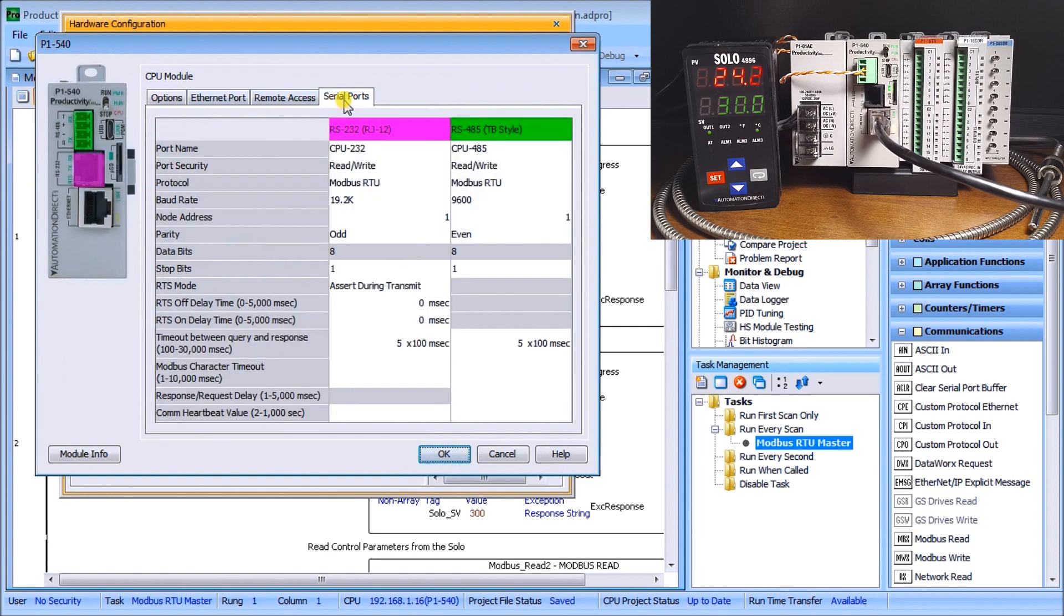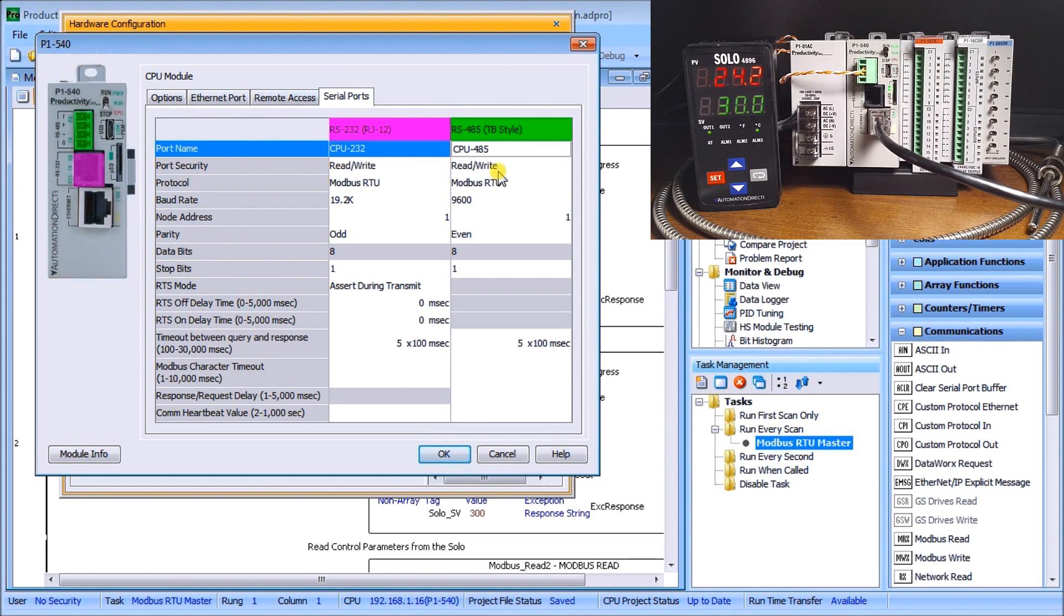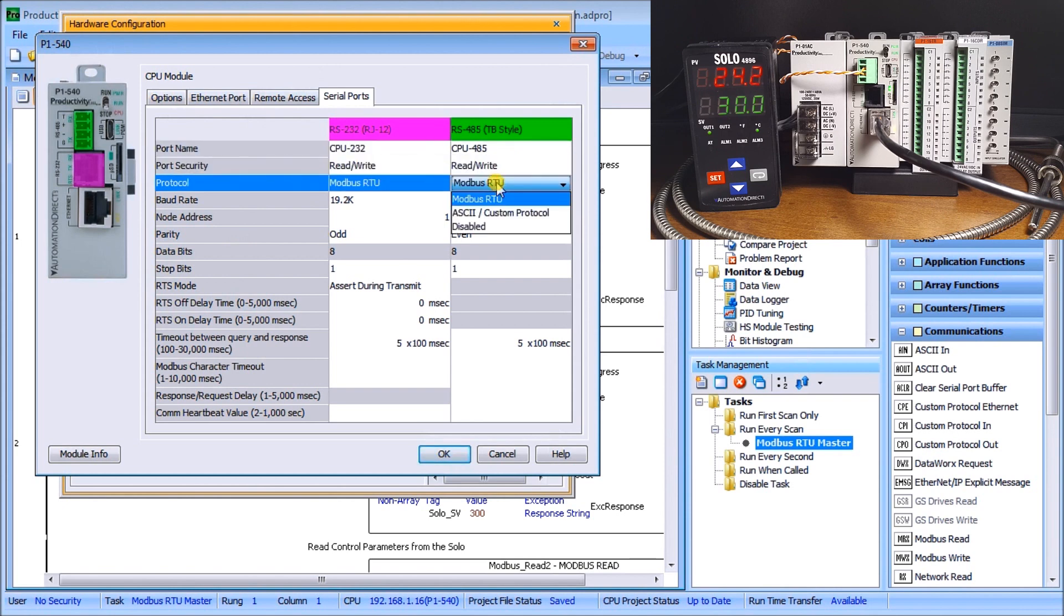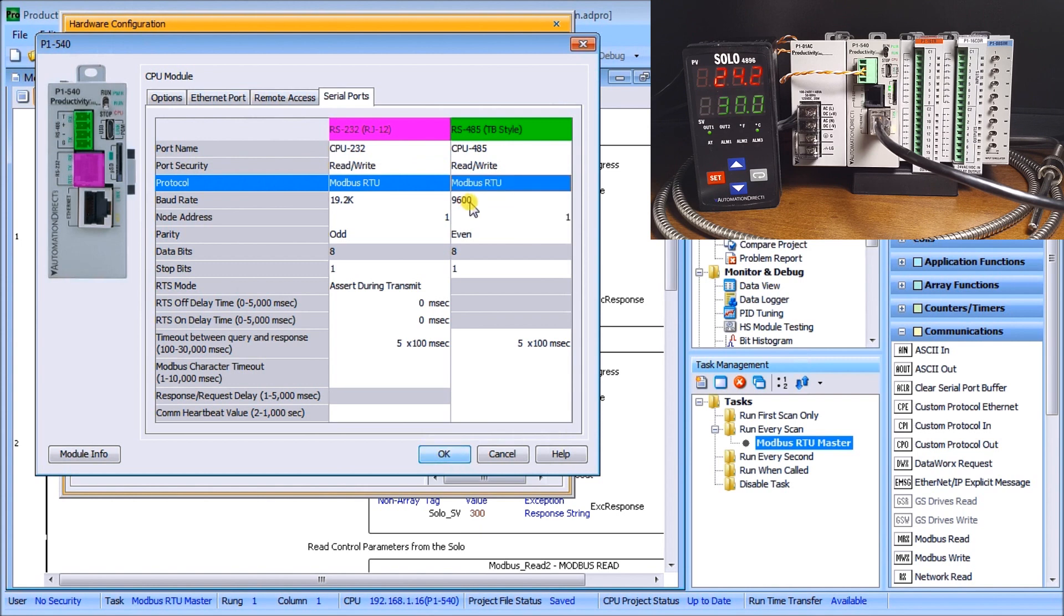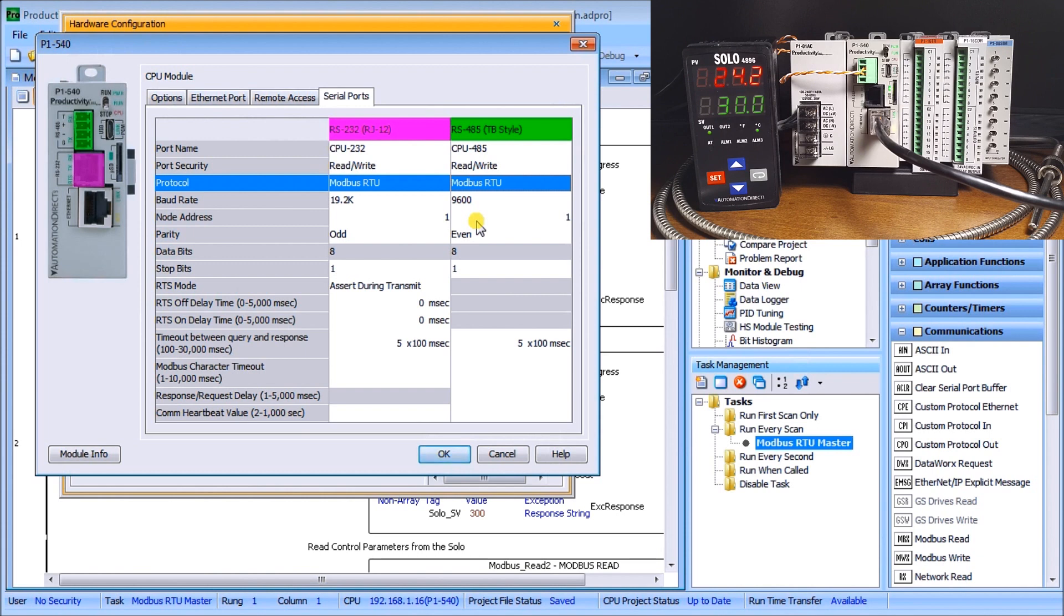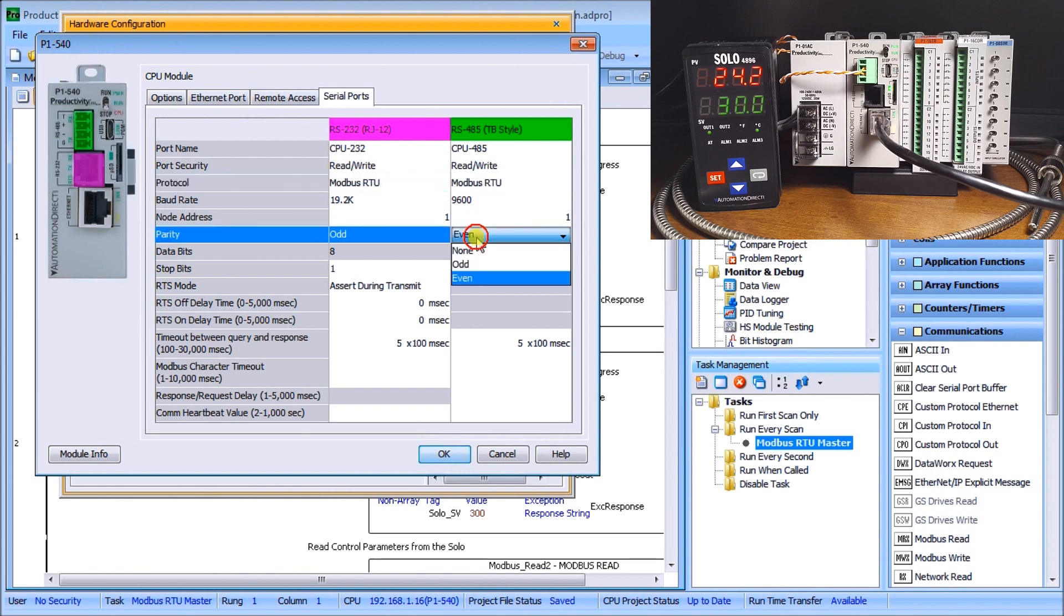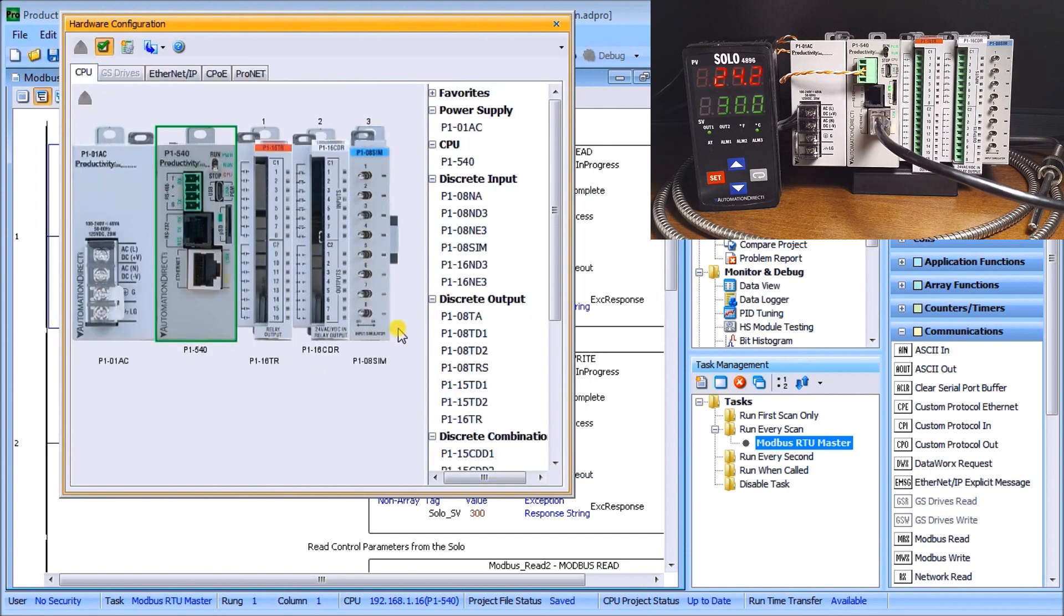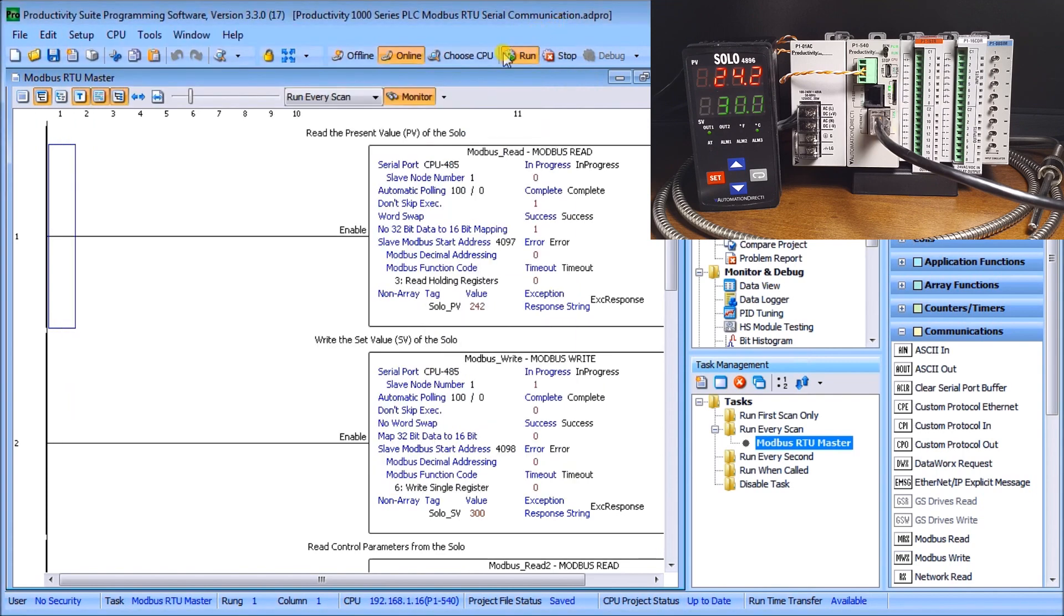We go to serial ports and under the serial ports we're using our RS-485 connector. We have our read write set for modbus RTU, then we have our baud rate 9600, our node address is one. Because we're using productivity as the master in this communication that node address is really irrelevant. Then we have even parity, we have eight data bits and we have one stop bit. Everything else left to default so everything looks good.